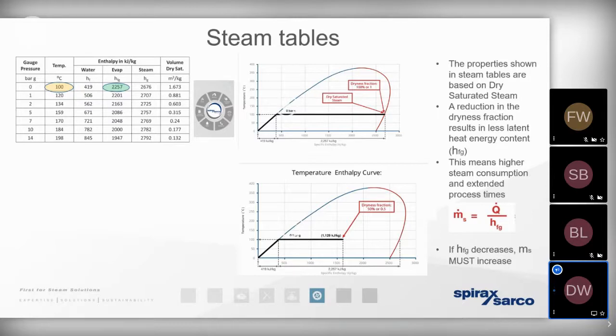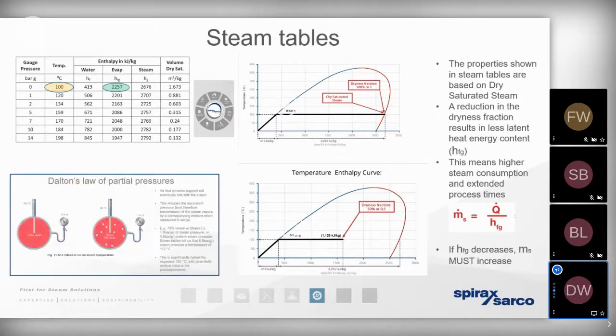And in the bottom of the two curves, you can see the example of us having a dryness fraction of 50%. In other words, the steam's 50% dry, 50% wet. That means there's 50% of the useful energy contained within the steam. So of course, if that is the case, and we're supplying significantly wet steam to a process where the heat exchanger has been sized on the assumption that the steam is 100% dry, then essentially the heat exchanger is undersized. It means it's going to take longer and longer for us to get the required heat energy into the process. So the process time can extend and extend, or it could well be that we just fail to hit the required process temperature altogether. And if we take that one step further and add in the fact that we may have air and other non-condensable gases entrained within that steam, then you can appreciate it makes it increasingly difficult to ensure that we're reaching the required process design conditions.